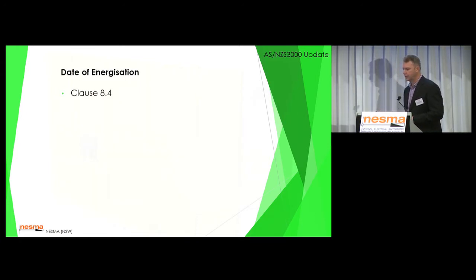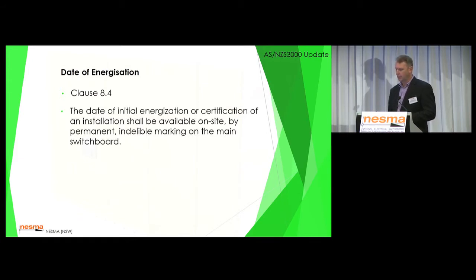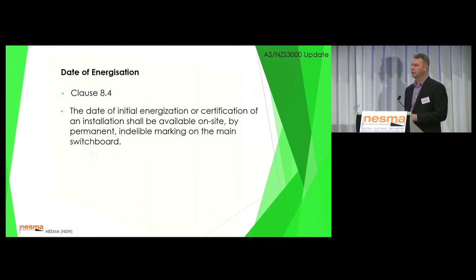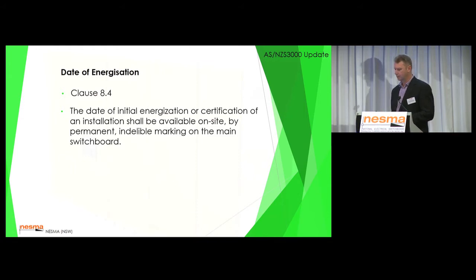Date of energisation. Again, just another small one, clause 8.4. The date of initial energisation or certification of an installation shall be available on site. So we currently have a date of manufacture on most of our 61439 or 3439 labels. This is a date of energisation. This would be an interesting little trick, that we may have to supply some extra labels after the switchboard's been installed, but from a manufacturing point of view, just a little one to remember that's made its way into the standard.